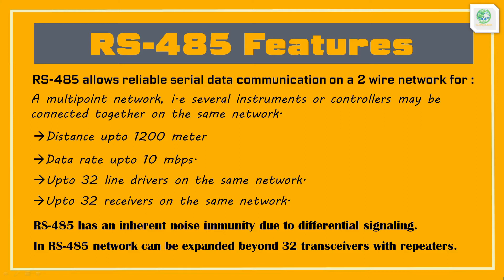RS-485 works really well in noisy environments due to its inherent noise immunity, as it uses differential signaling. In a RS-485 network, if more than 32 transceivers are required, repeaters could be used to extend the network.